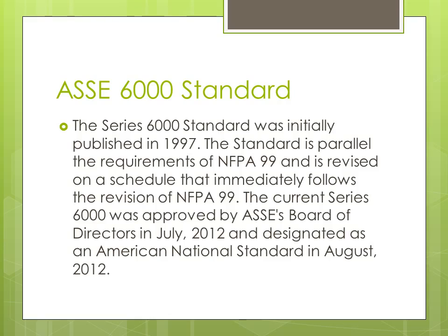Do the maintenance folks need to have an ASSE 6000 type certification? There are different levels, 6010 and 20 and 30 and 40, 50, I think, and 60. The answer, as I have read it and as I've talked to others, is no, probably not. Most maintenance folks, the kind of services we do are external to the pipe. We might change an O-ring, we may address the outlet, but that's as far as we go. And I don't believe the ASSE standards were meant to address those types of situations.